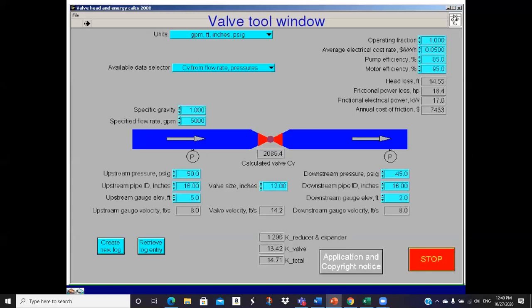And what is the annual cost? Say that if that valve sits in that position for a year and you continue to put 5,000 GPM through it under these operating conditions, it's going to cost you $7,433 in pumping energy. If that sits that way all the time, we could open up that valve and trim an impeller, or put on a VFD. We have other ways to reduce the flow that don't waste the energy.